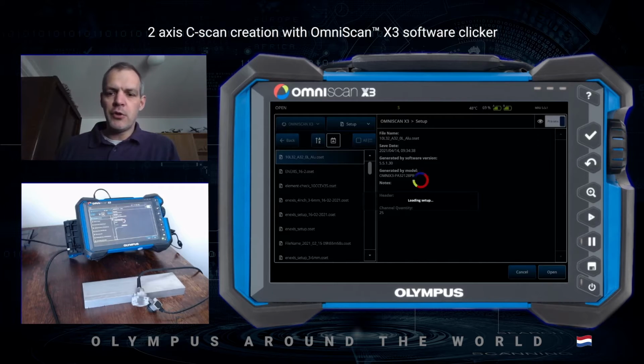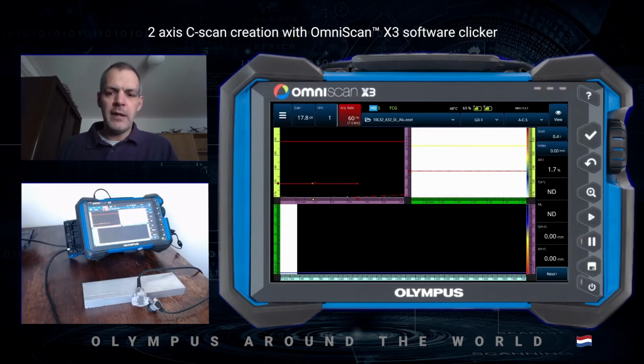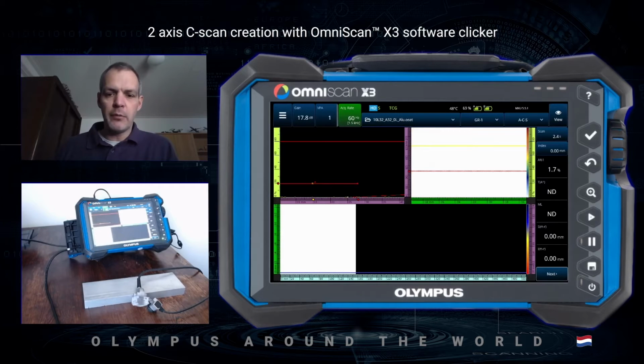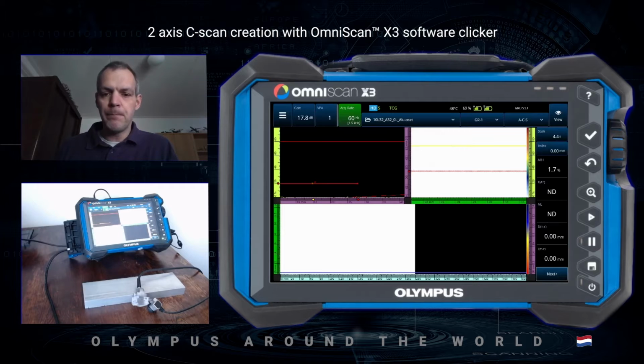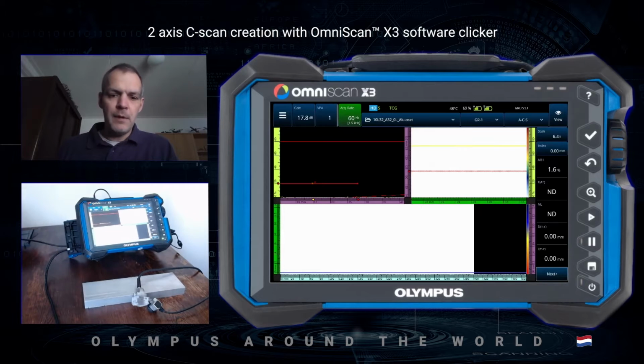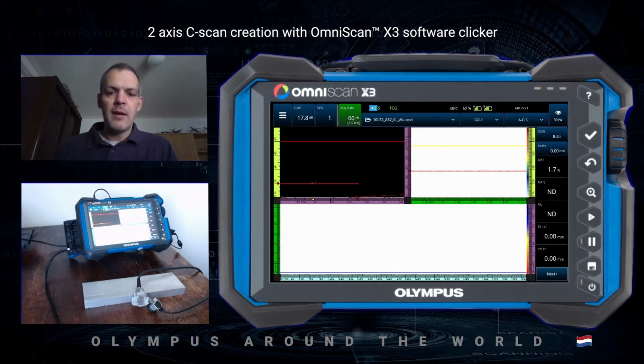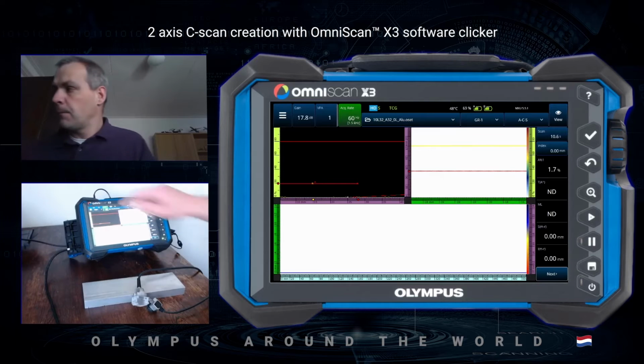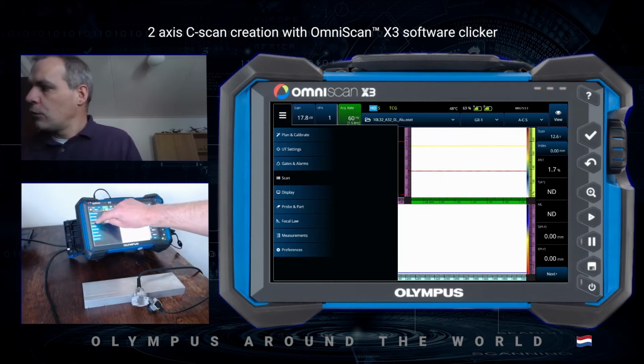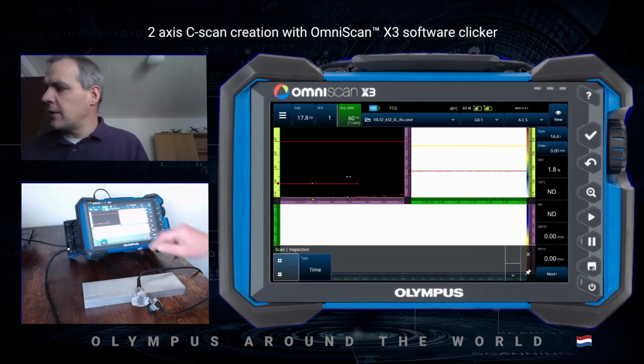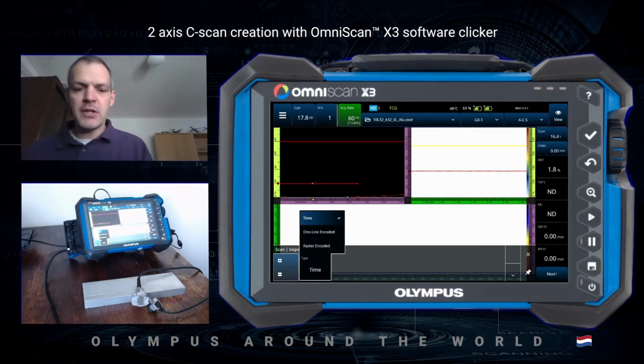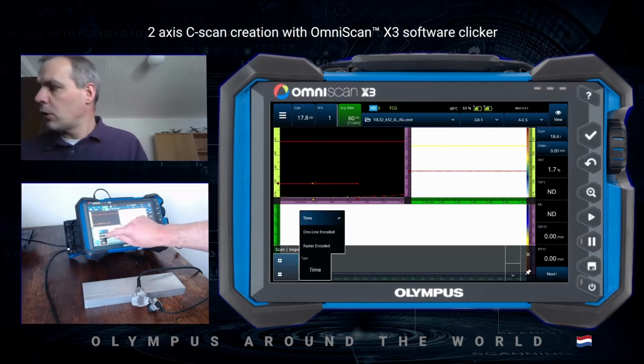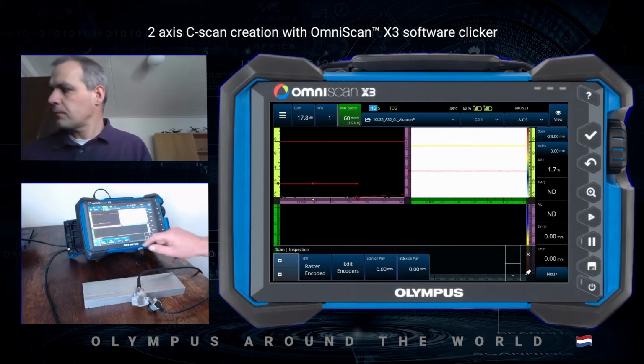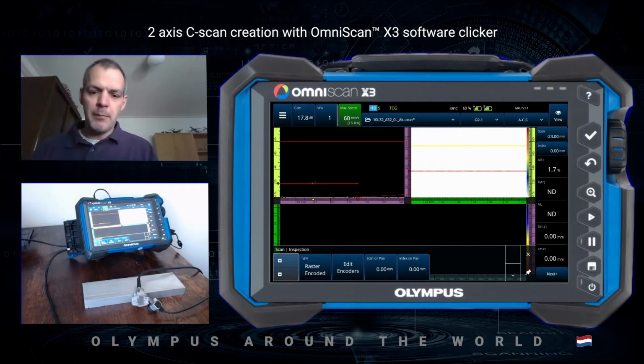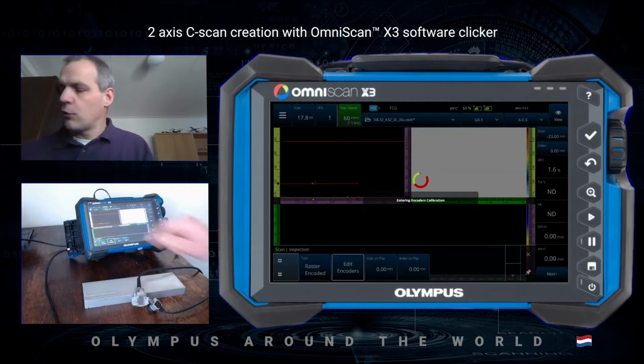I also adjusted some views, so when recalling the file, the A, C and S scan automatically appear on my screen. Next step is that I have to tell the instrument that I want to make a raster scan. Go to the scan menu, select inspection and change the inspection type from time to raster encoded. Some additional buttons appear.